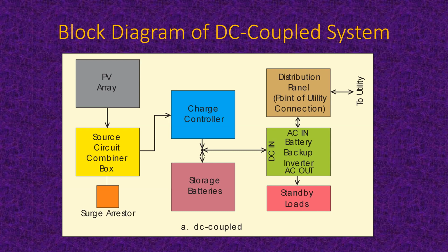Once it gets to that battery backup inverter, that starts making electricity, and maybe a lot. The first choice for that electricity is to go down and meet the needs of the standby loads. Once the standby loads are satisfied, then any leftover electricity from that battery backup inverter goes up to the main distribution level.